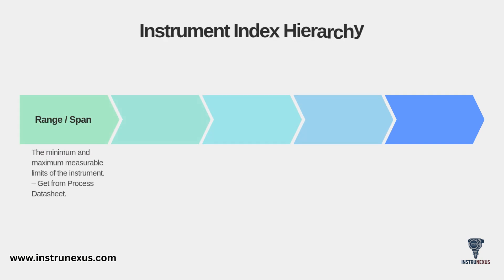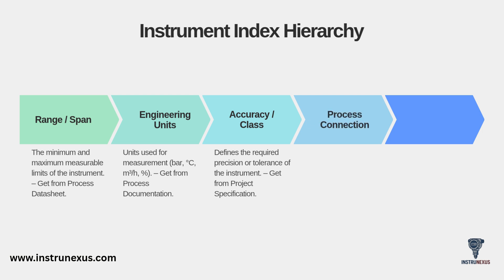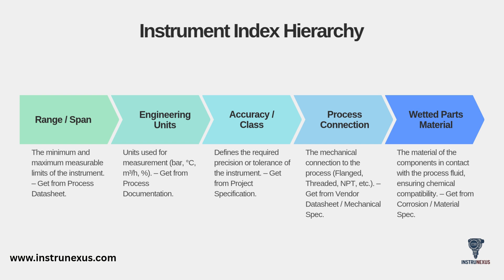Continuing with the Index Hierarchy, we get into more specific engineering details. You must define the range or span — the minimum and maximum measurable limits of the instrument, obtained directly from the process datasheet. Alongside this, you list the engineering units, such as bar, degrees C, or percent. You'll also specify the required accuracy or class, which defines the instrument's precision and is usually found in the main project specification. Then come the physical details: the process connection type, like flanged or threaded, and the wetted parts material — critical for ensuring chemical compatibility with the process fluid, from the corrosion or material specification.